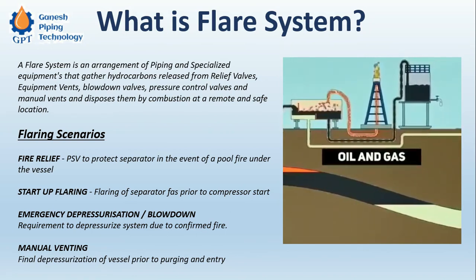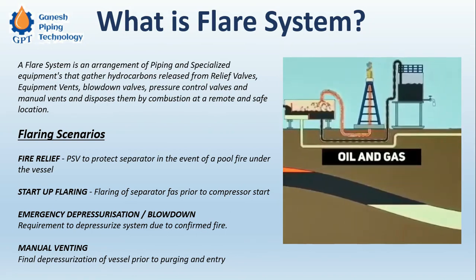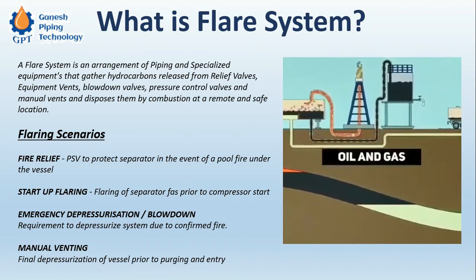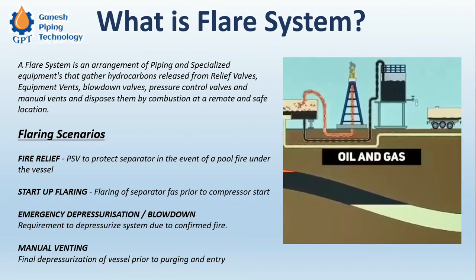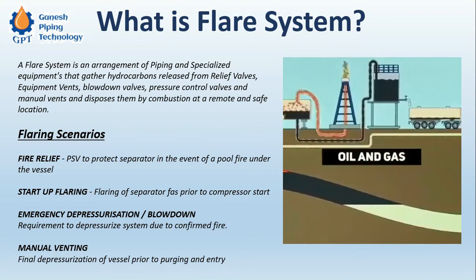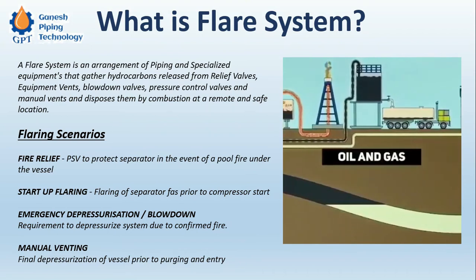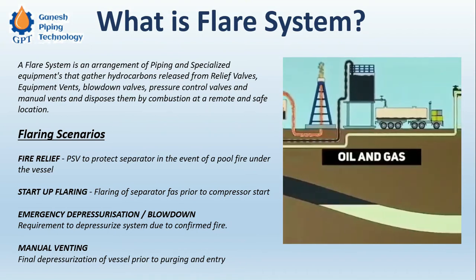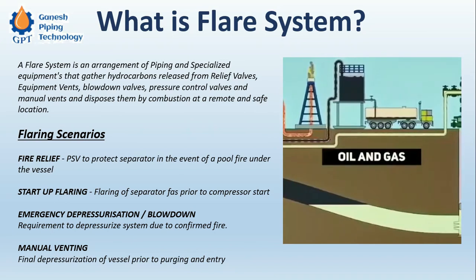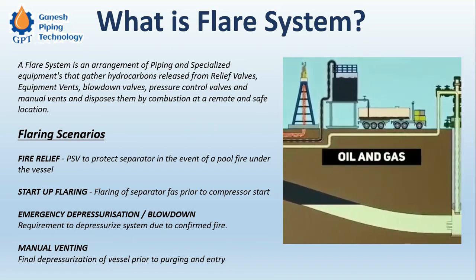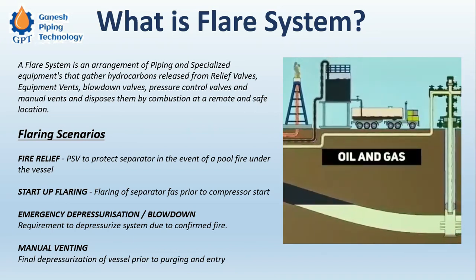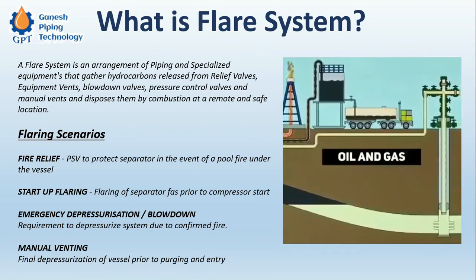Emergency depressurization is another scenario — a blowdown requirement to depressurize the system due to a confirmed fire. There is an emergency system wherein, if there is a fire, all systems are automatically shut down and whatever piping and systems are present are depressurized and connected to the flare, where the pressurized gases are burnt off.